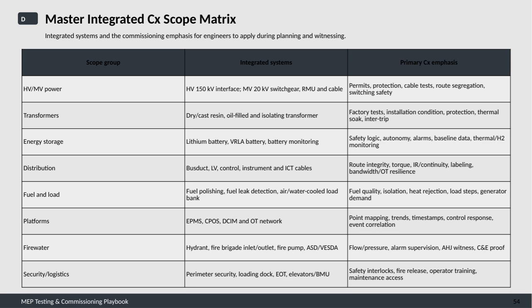For transformers, whether dry, oil-filled, or isolating types, the focus is on factory testing, verifying insulation conditions, protection settings, thermal soak monitoring, and inter-trip functionalities. Energy storage systems like lithium and VRLA batteries require attention to safety logic, autonomy settings, alarm functions, baseline performance data, and monitoring for thermal conditions or hydrogen buildup. In the distribution category, which covers bus ducts and low-voltage control and instrument cables, it's critical to verify route integrity, torque of connections, insulation resistance and continuity tests, proper labeling, and resilience of bandwidth or operational technology.